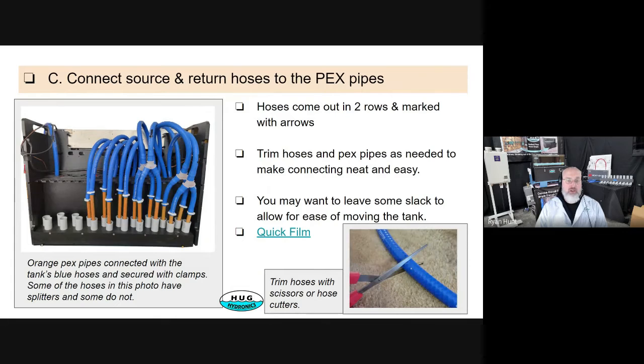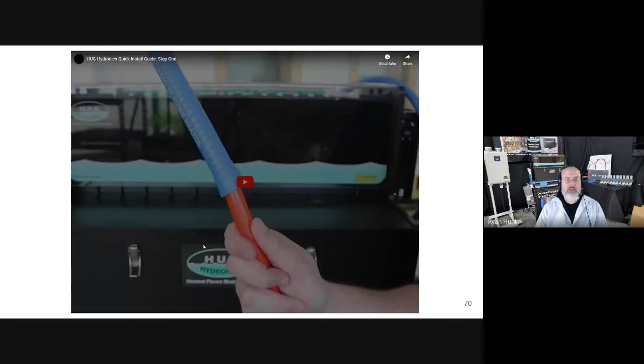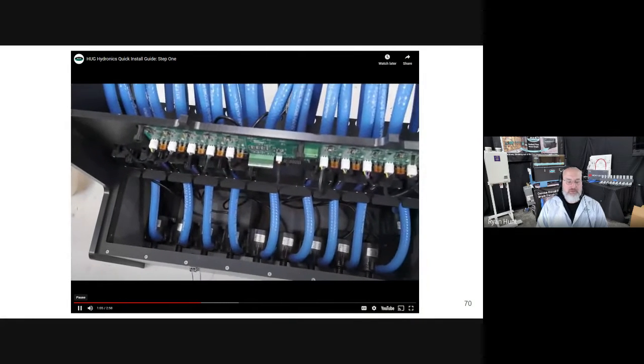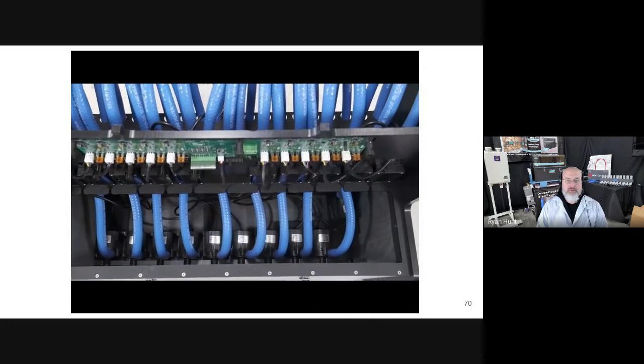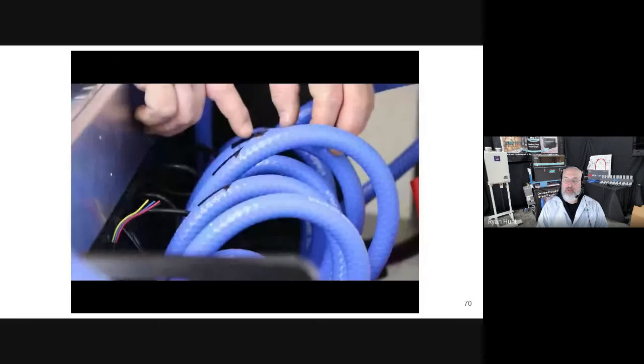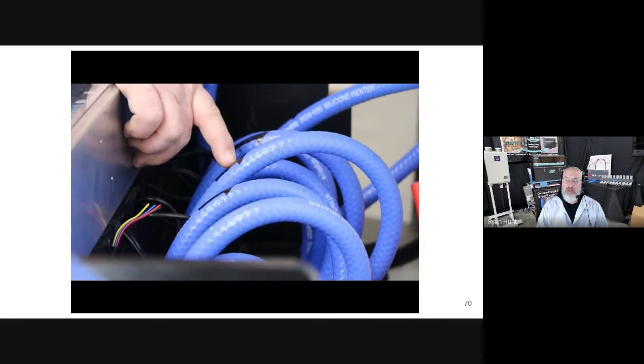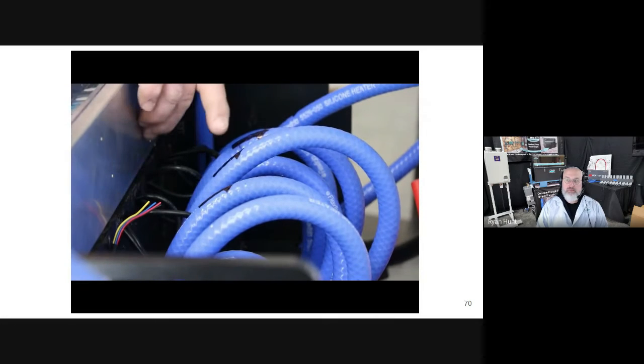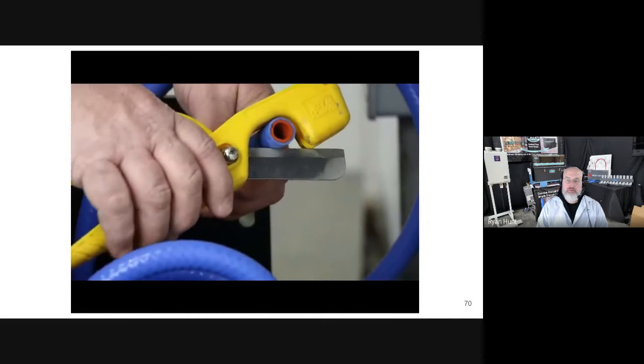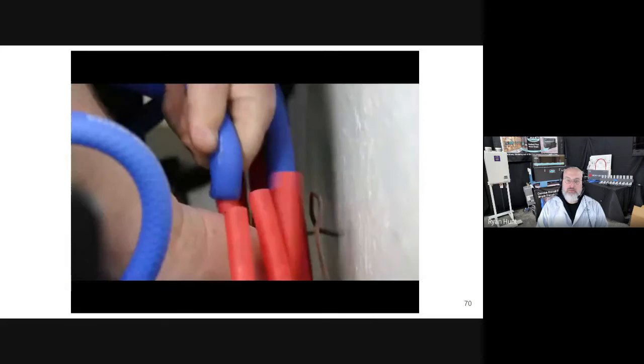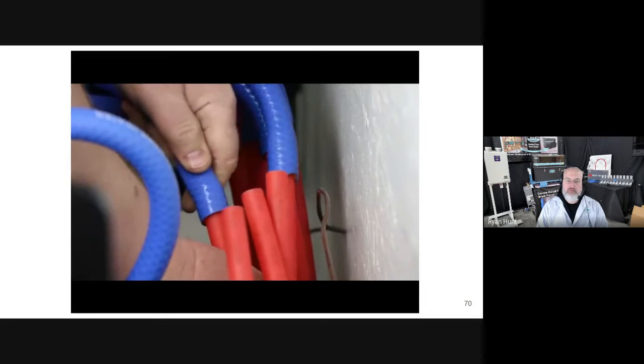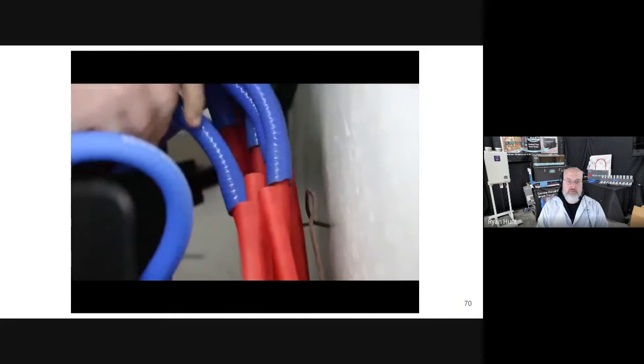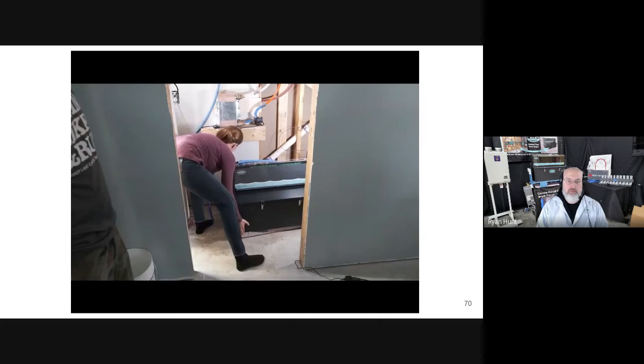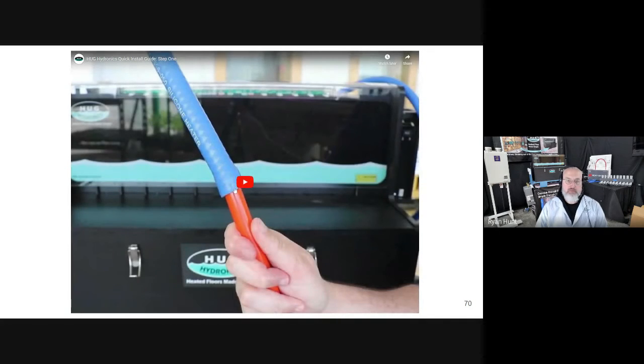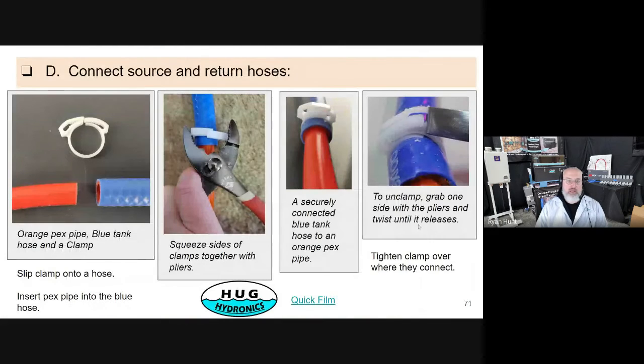And now we'll connect the hoses. And I have a little video for that, which says it better than I can. Next, we'll connect the source and return hoses to the PEX pipes. Note that the hoses come out in 2 rows and are marked with arrows, indicating flow into and out of the tank. First, trim the hoses and PEX pipes as needed to make connecting neat and easy. You may want to leave some slack to allow for ease of moving the tank. So pretty easy.